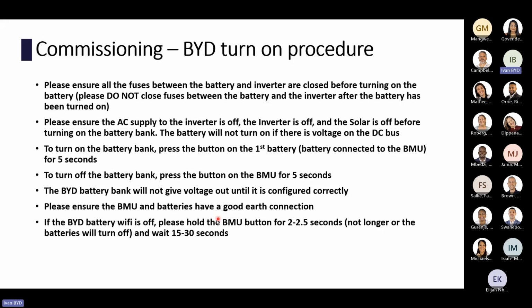The BMU has a feature where after 5 hours, the Wi-Fi will turn off. So if you get to a site and you want to update the firmware and everything's running smoothly, but the Wi-Fi is off, you just hold the BMU button for 2 to 2.5 seconds, and then wait 15 to 30 seconds. Holding the BMU button for 5 seconds turns the battery on, so please try not to hold it too long.